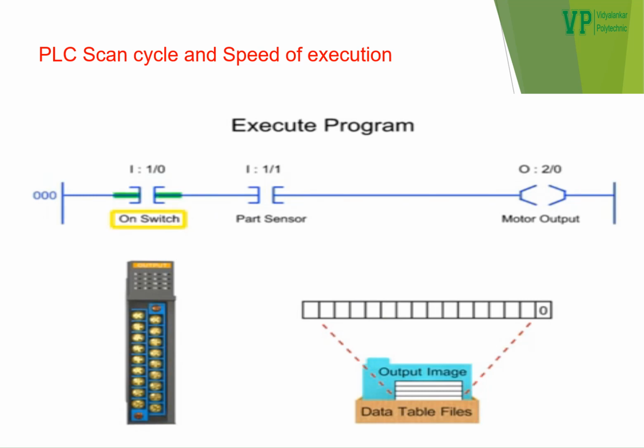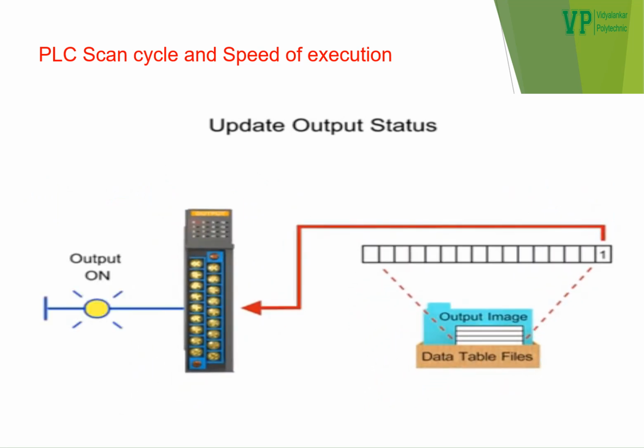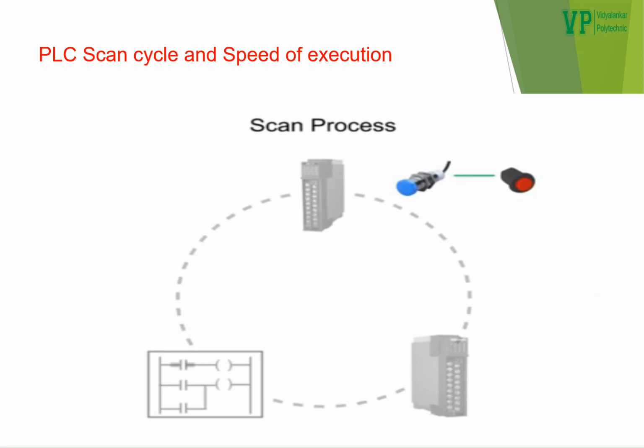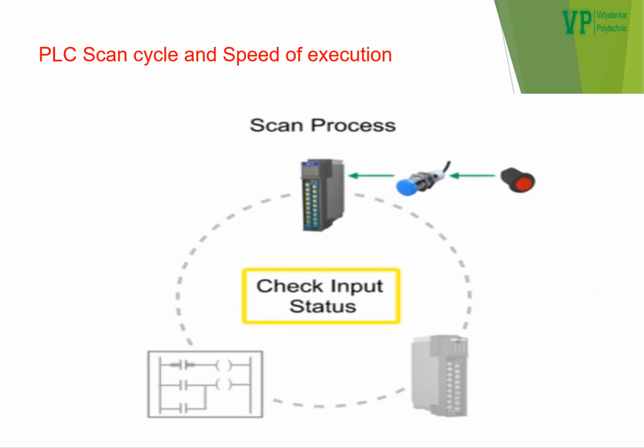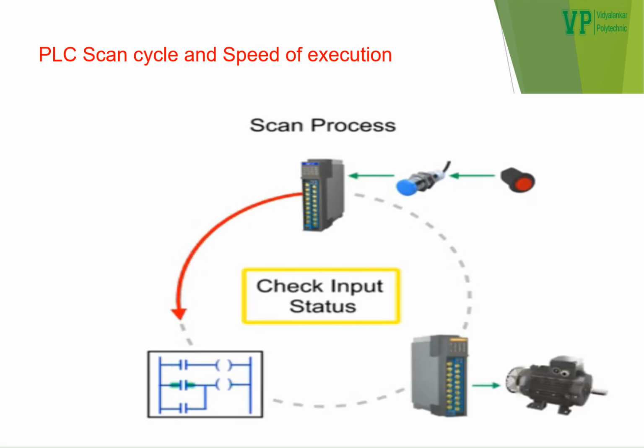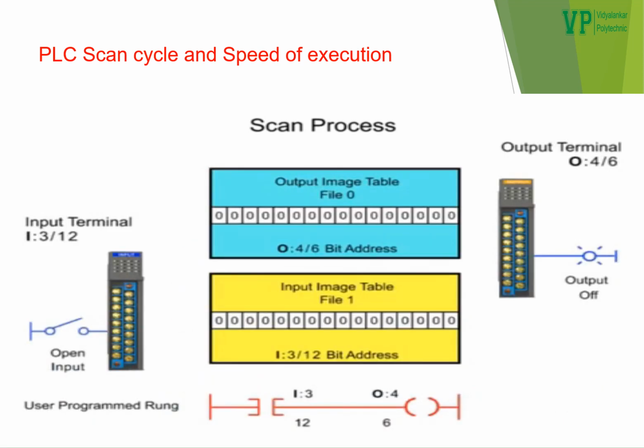all the instructions get executed one by one, and depending on the status of input, the output status gets updated in the output status file. During the last phase of scanning, the output gets energized or de-energized depending upon the status of the output status table. After the last phase of scanning cycle, the entire scanning process starts again. That is, check input status, execute program, and update output status. Let's have a look at the animation once again.